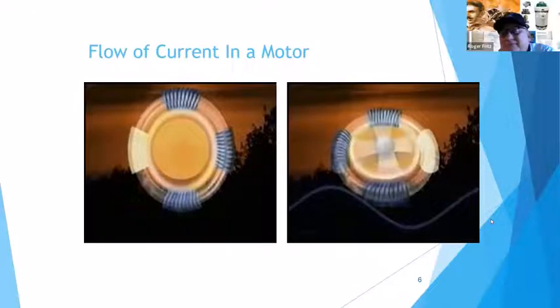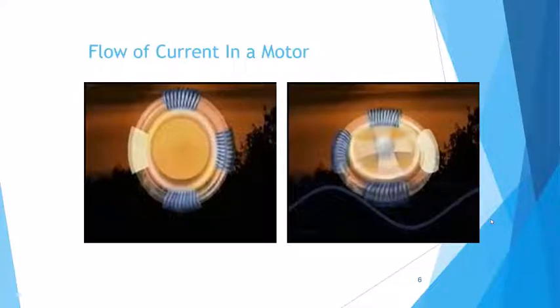What we see occasionally on commercial jobs with VFDs is just a lot of noise. About all we can do is put a capacitor across the primary power or something. Often that calms it down, but the finger really points at us at times that it's our equipment. It could be, but oftentimes when we get things separated out and get the VFD tuned, then that all settles down. What's our best step moving forward?